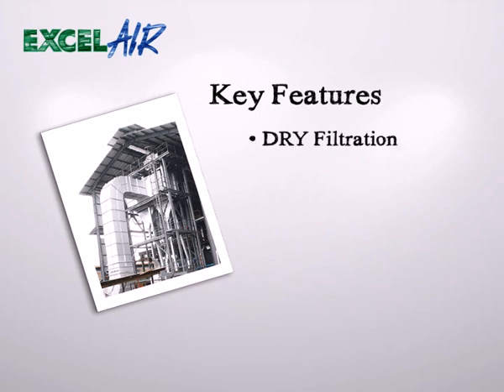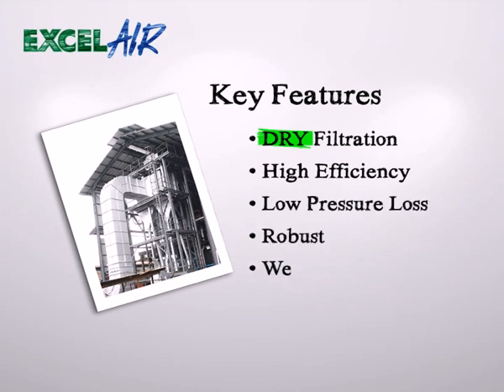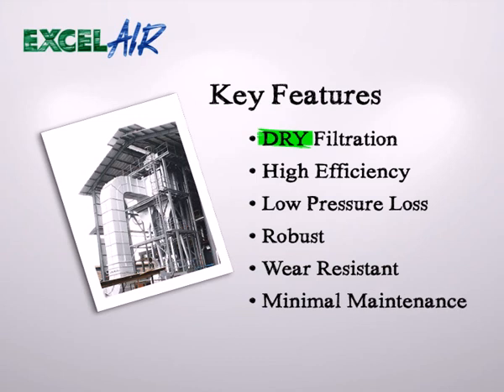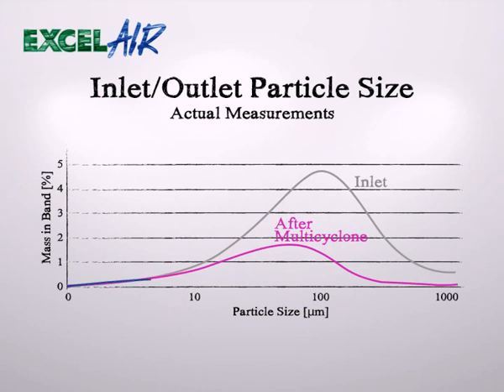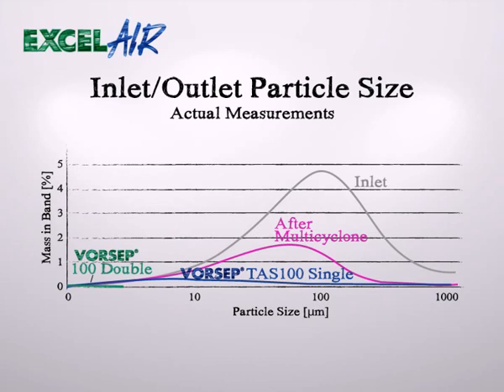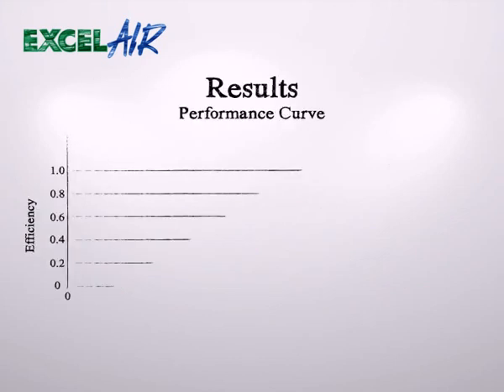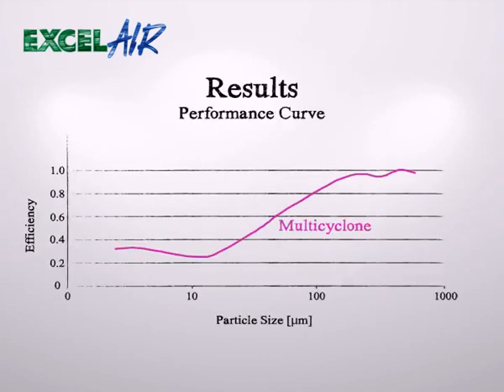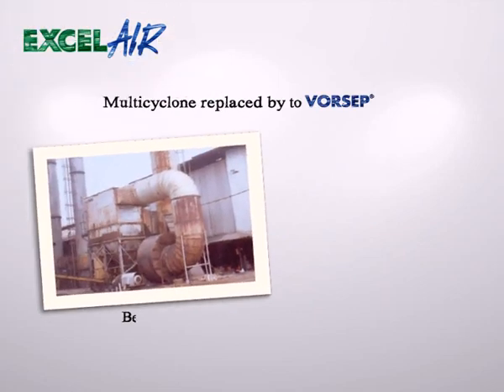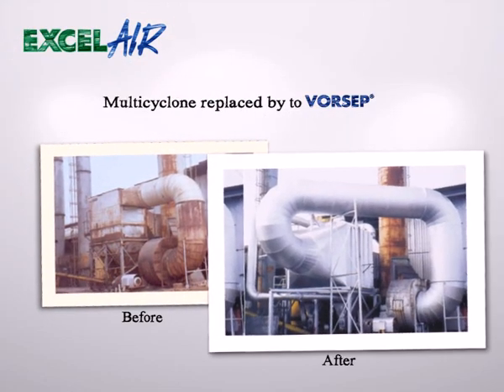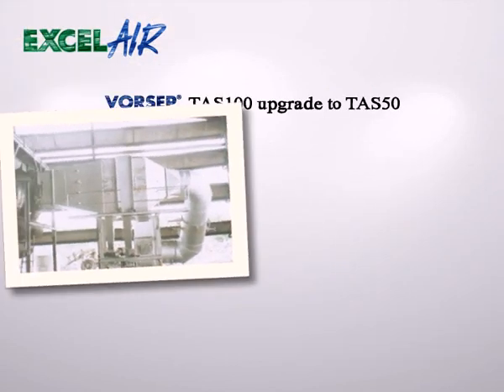Key features include: dry filtration, high efficiency, low pressure loss, robust construction, wear resistance, and minimal maintenance. Looking at the particle sizes again, the VORSEP not only reduces the particle sizes, but also collects particle sizes over the whole spectrum. Consider the vast difference between the VORSEP reduction over a comparison multi-cyclone reduction. The efficiency curve of the VORSEP compared to typical multi-cyclones puts the efficiency of the VORSEP system into perspective. Because it is compact, the VORSEP system can be retrofitted into boiler installations by removing the existing multi-cyclone.